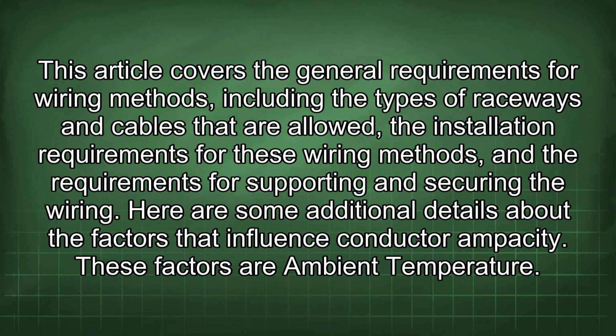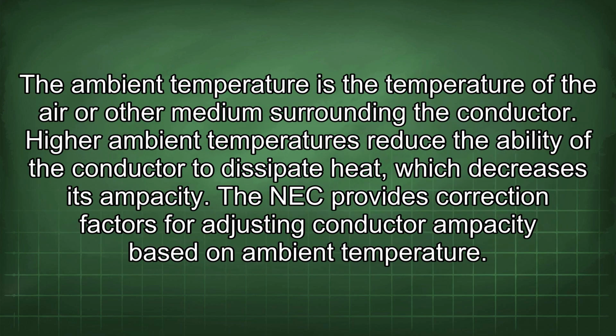Here are some additional details about the factors that influence conductor ampacity. These factors are ambient temperature. The ambient temperature is the temperature of the air or other medium surrounding the conductor. High ambient temperatures reduce the ability of the conductor to dissipate heat, which decreases its ampacity. The NEC provides correction factors for adjusting conductor ampacity based on ambient temperature.